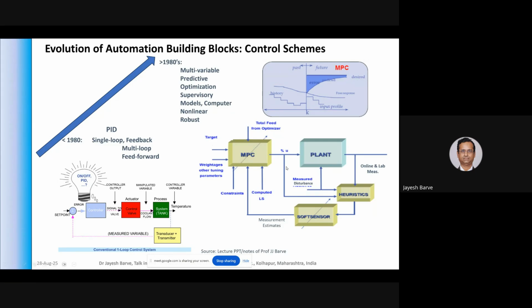So we built cement plant kiln and ball mill optimization. It's a control system running in the control room on a computer. The computer pulls data from the DCS and downloads set points to the DCS, so the operator just has to watch. He doesn't have to make the decision to download the set points. Earlier, when operators used to do the set point operation manually, they could not do it minute to minute—that's a human limitation. So the operator would change set points infrequently, maybe once in half an hour or whenever needed, taking action when he noticed something or when alerted, otherwise acting very slowly.